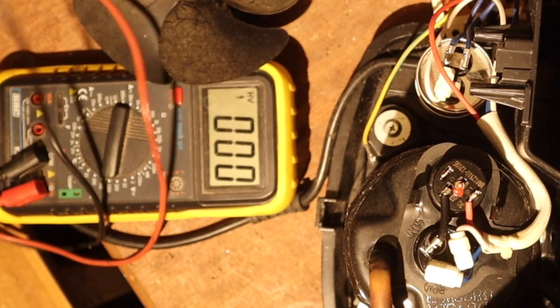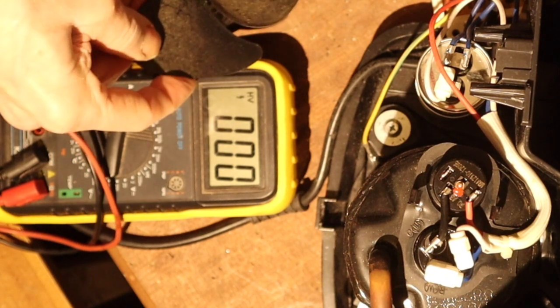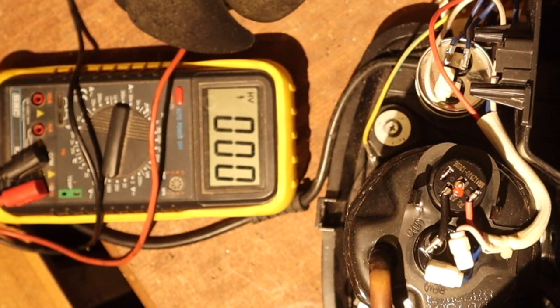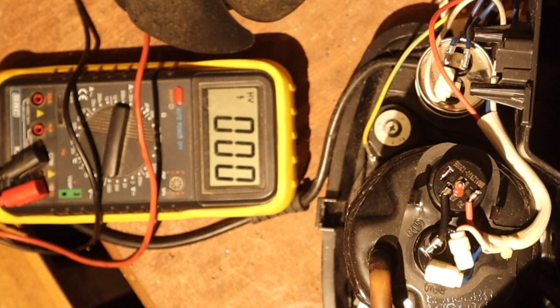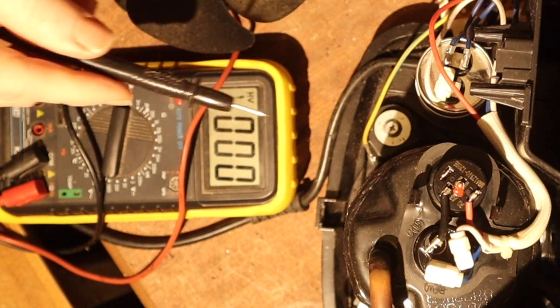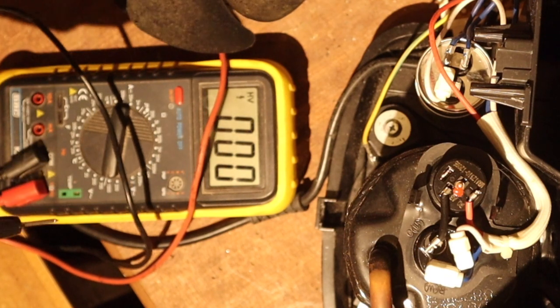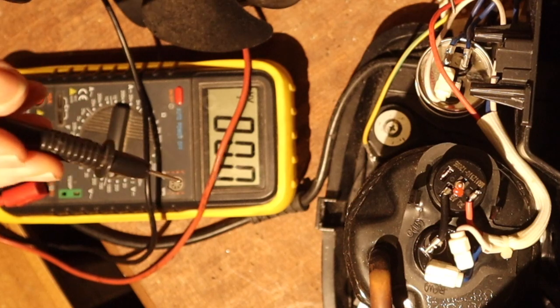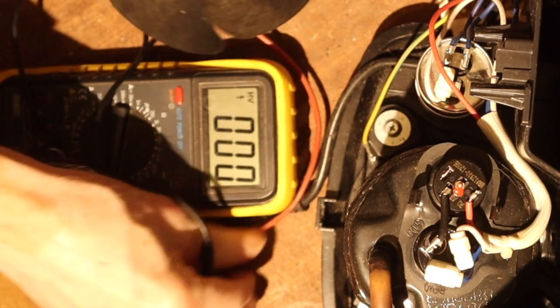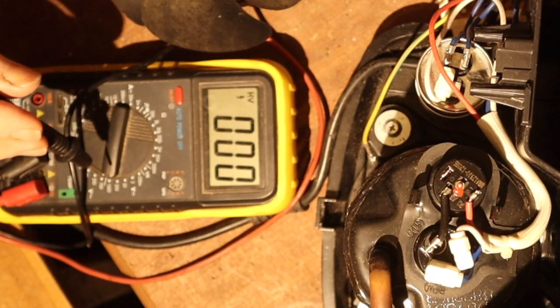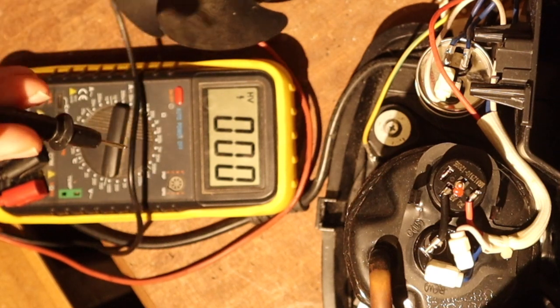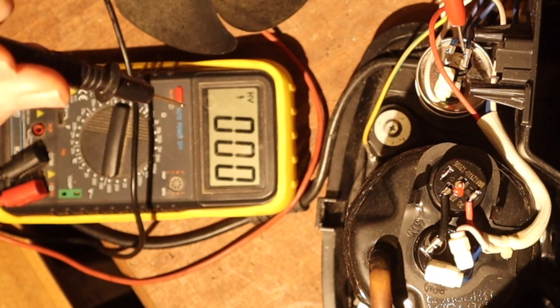Before we make this resistance measurement, I just want to check the state of the capacitor, which could still be at a dangerous voltage. So I put it on direct current, I apply the high voltage, and then I will test just between the contacts.